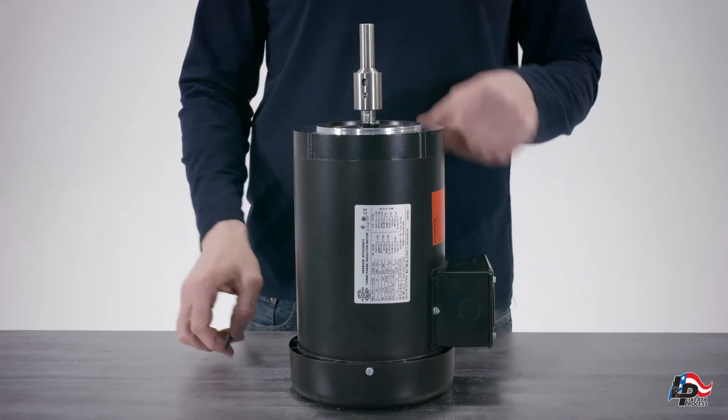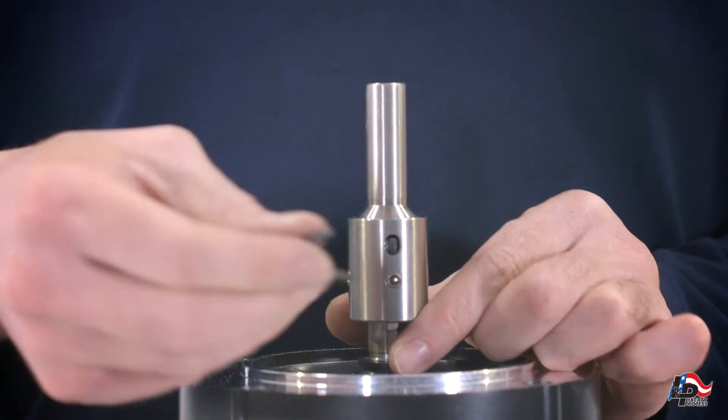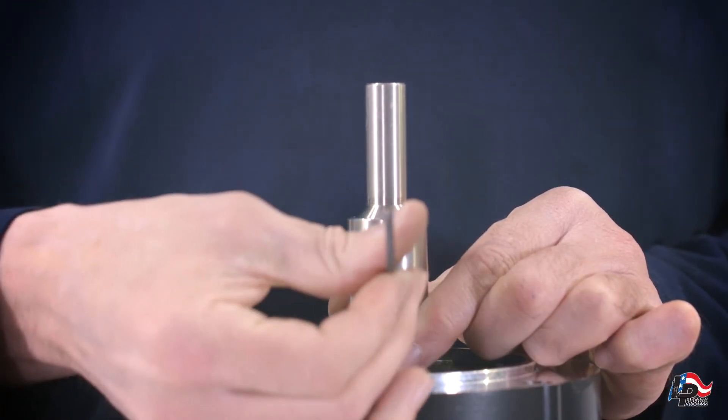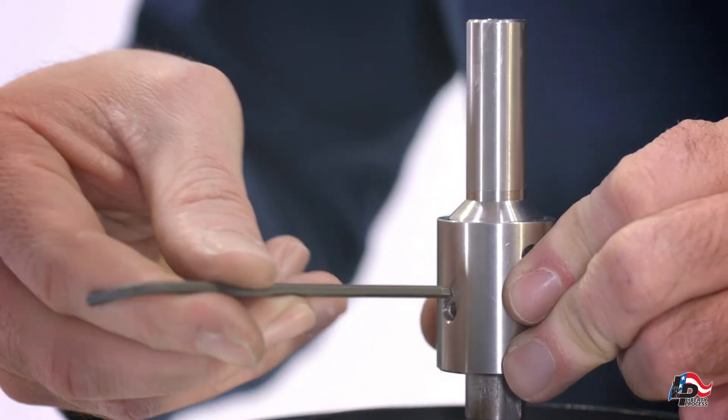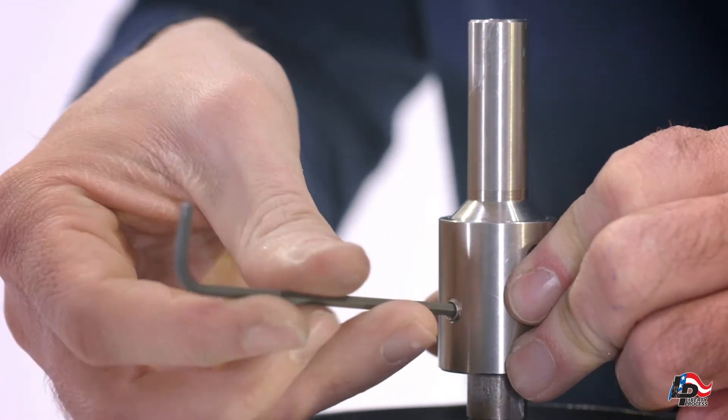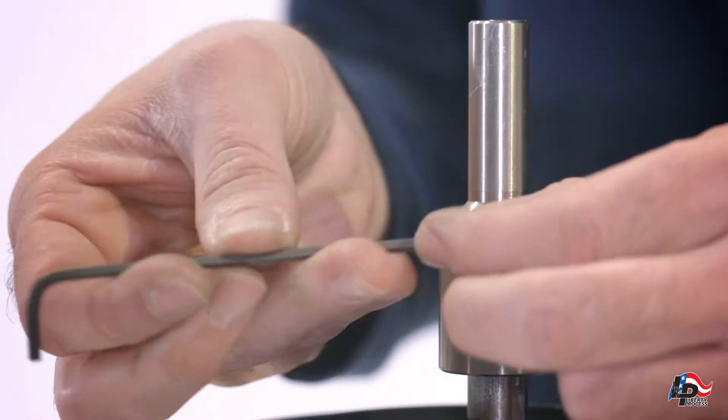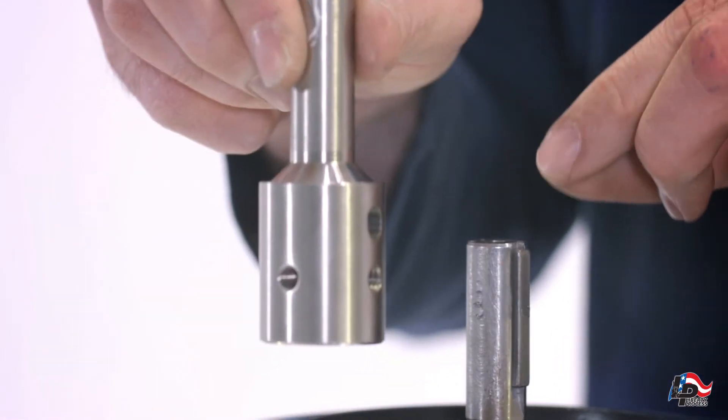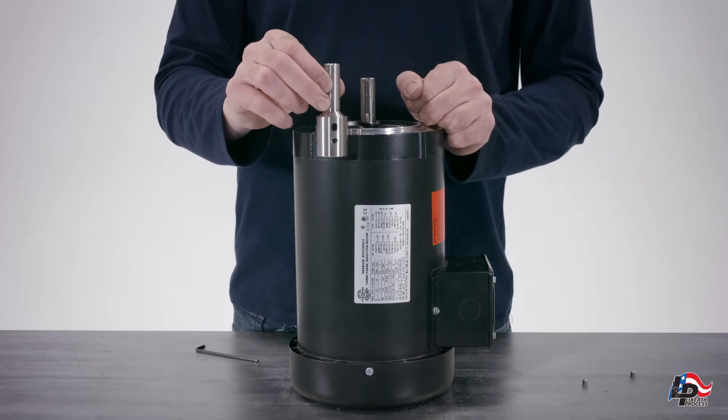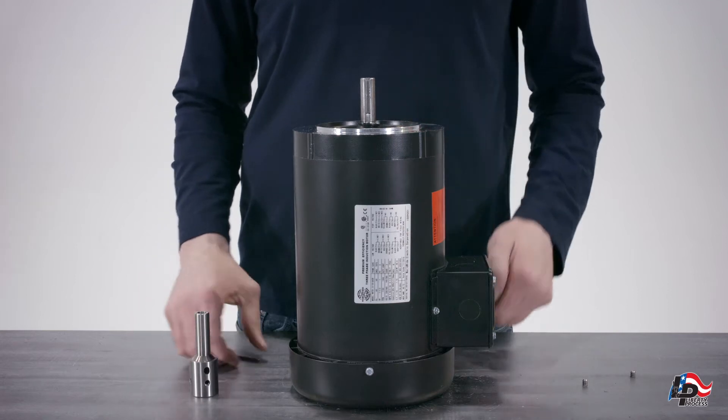Loosen and remove the two set screws from the pump stub shaft. Remove the pump stub shaft from the motor shaft. You have now completely disassembled your Liberty APM22 wobble stator pump.